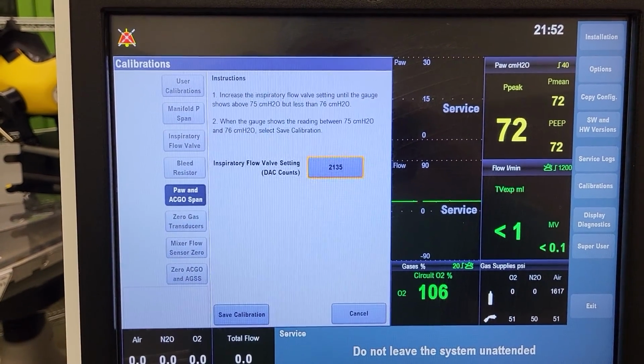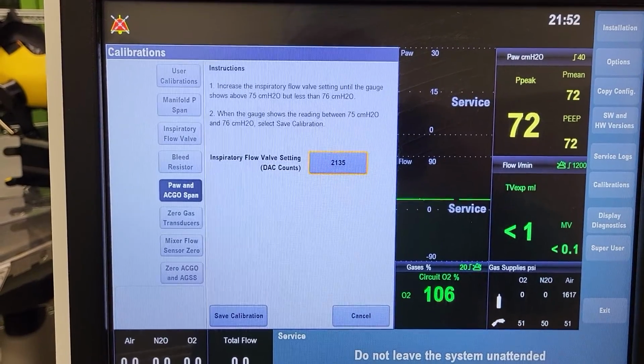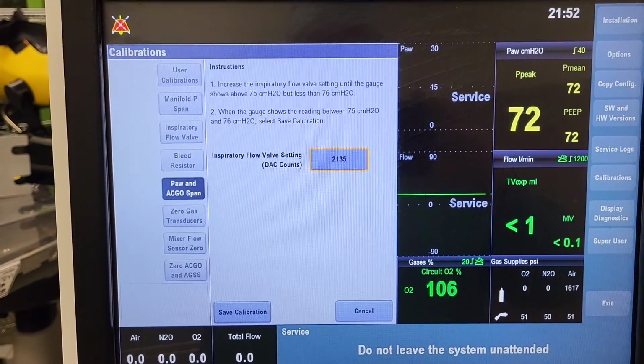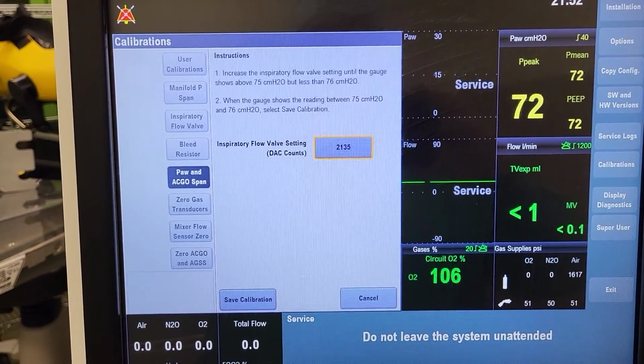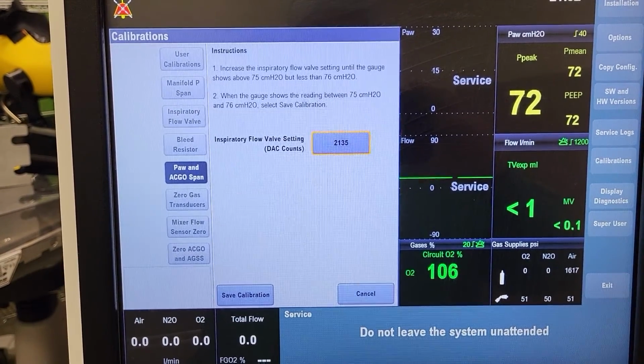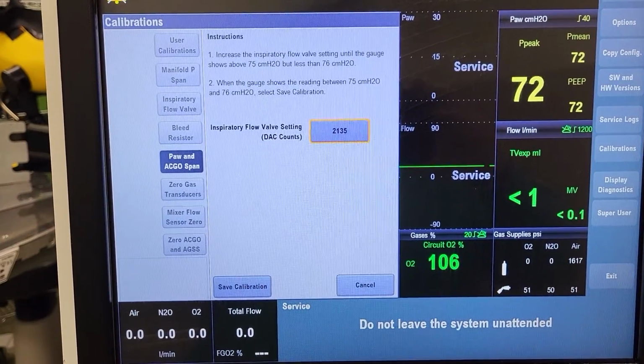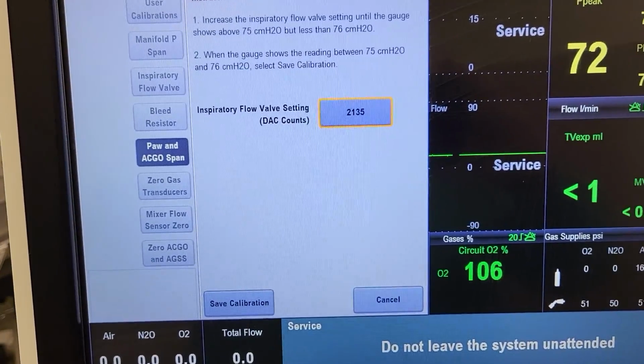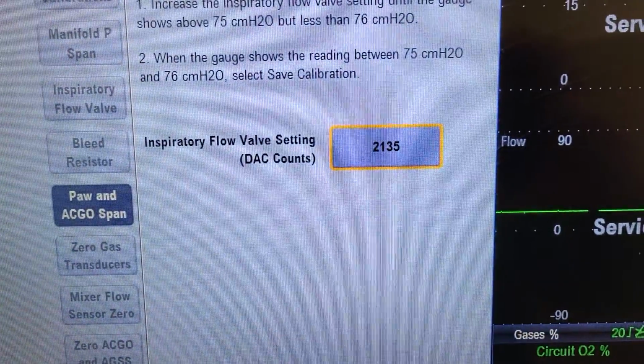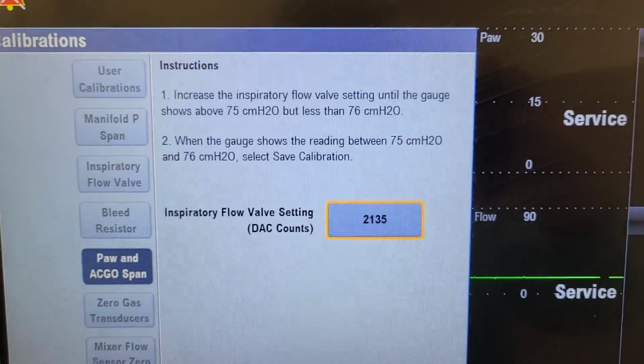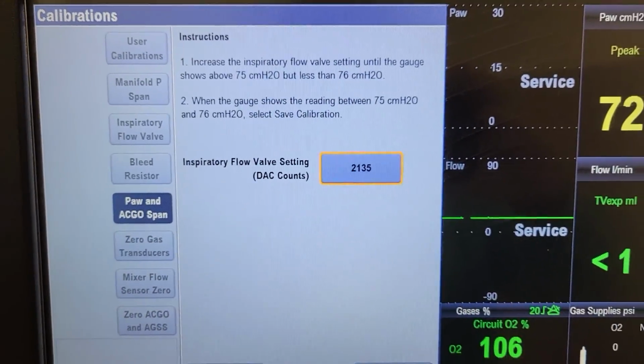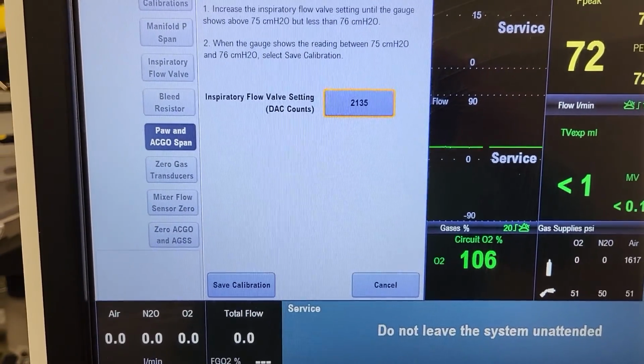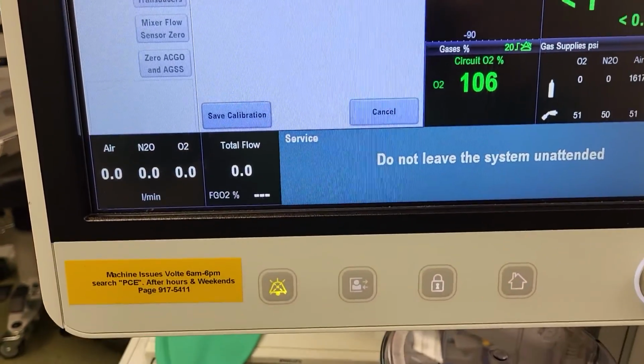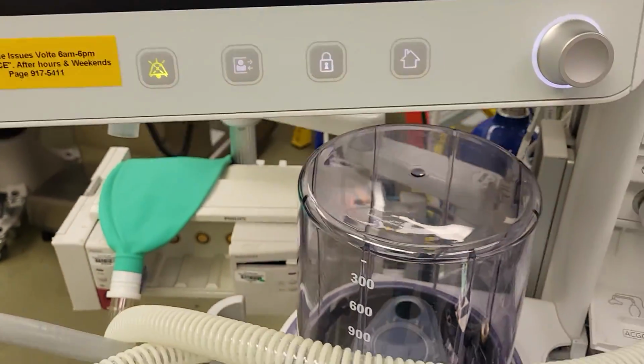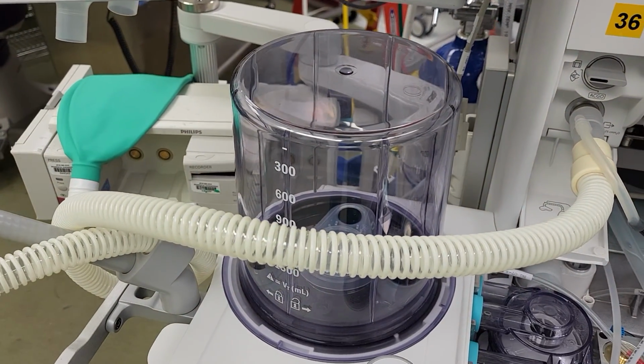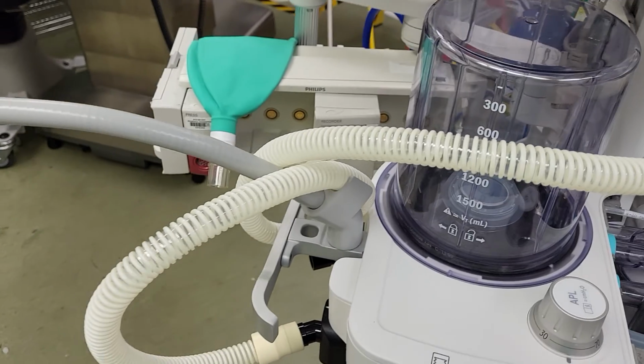Okay, here we are on the GE Carestation 650 again, and we had just done a video prior to this to show you the setup for the airway pressure and ACGO span calibration. And then we hit start, okay, and then we increase the DAC count right here, just like it says in the instructions, until the pressure gauge reads 75 centimeters of water. Now the important thing about this cal is to make sure you're at the top, teetering on 75 and 76, but still on 75. Okay, here's our setup again.